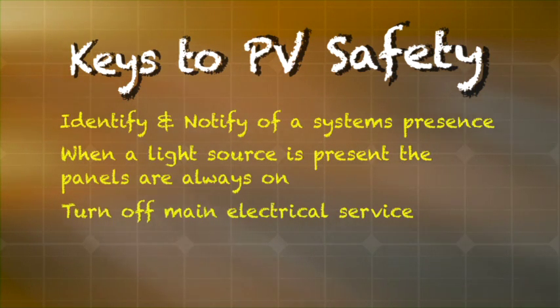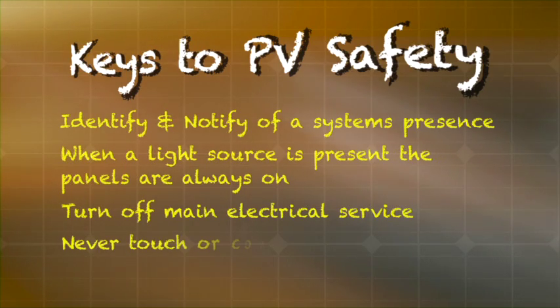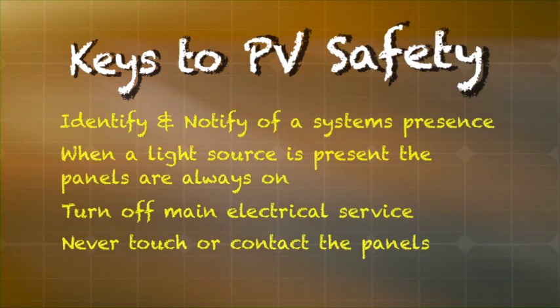If a rescue's involved, that takes priority, but as soon as you can turn off the main service, the safer everyone will be. When you've shut off the main electrical panel, know that there is still DC power from the rooftop down to the inverter. Don't touch any of the other panels. Don't walk on them. Don't try to unplug them. Just stay away from them.